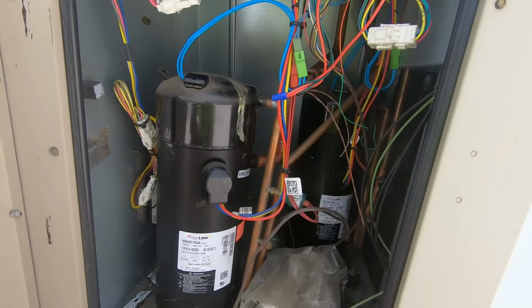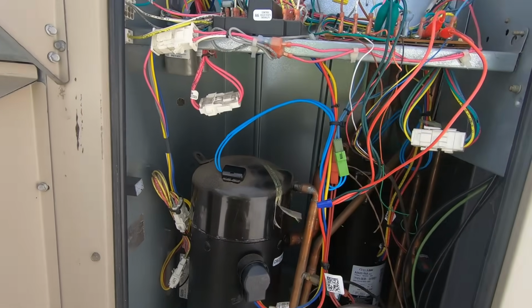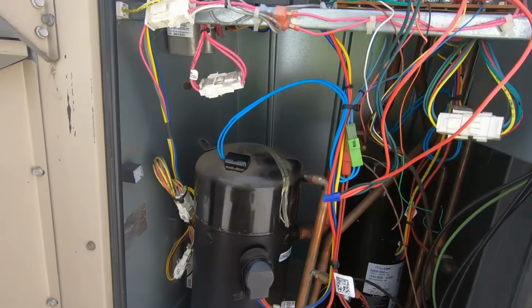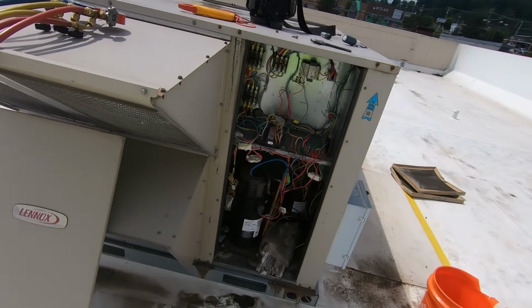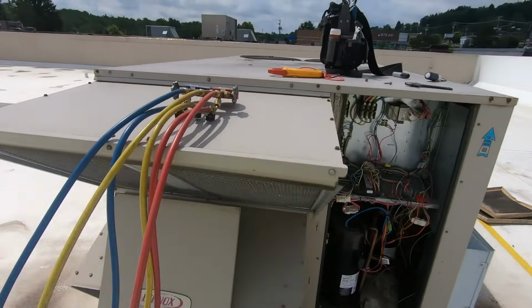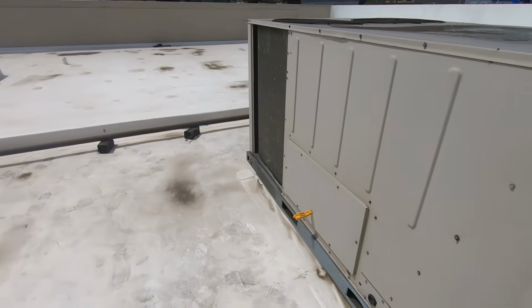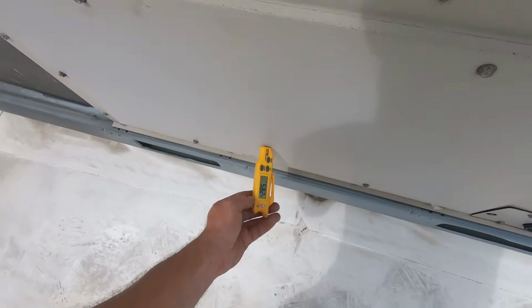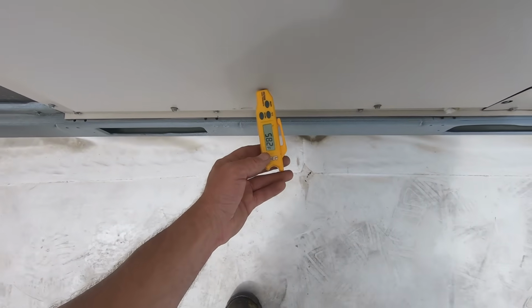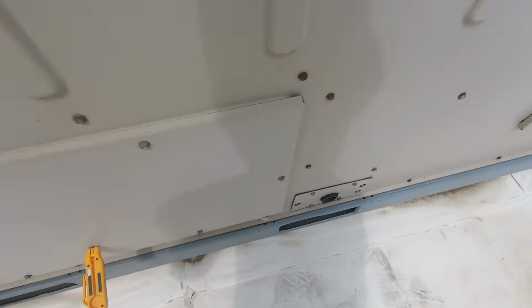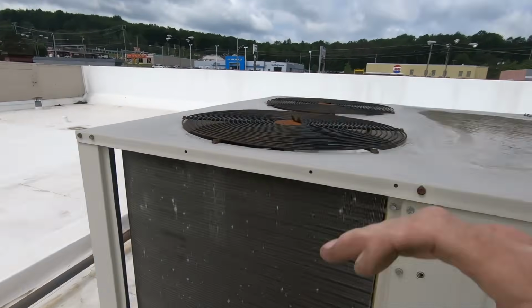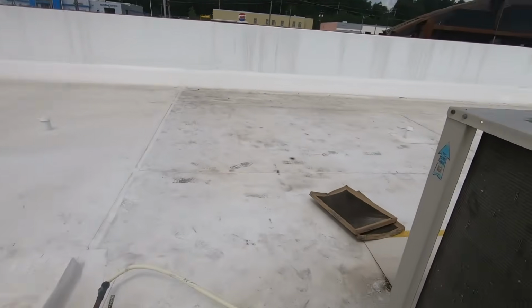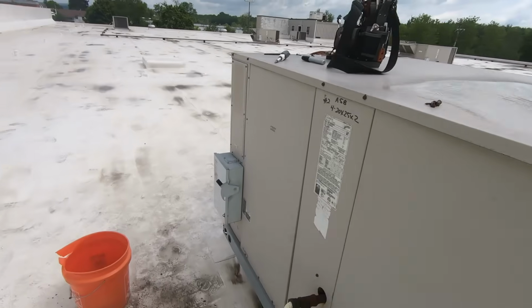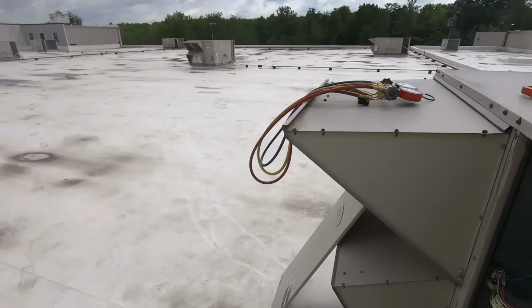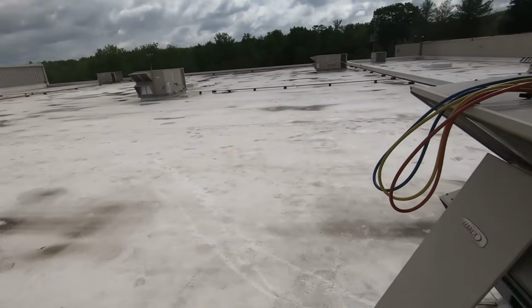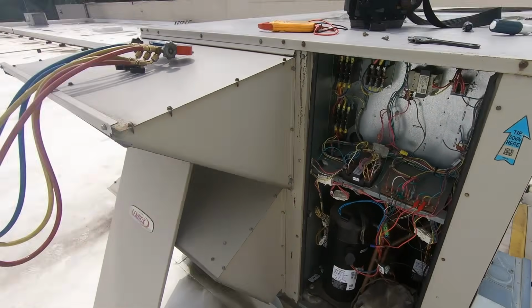Come back, clean it. I always put on the service report after they're cleaned and maintained. There may be more write-ups. So, well, I'm glad that we don't have any major problems with this guy. I think that guy hit the switch and turned the power off to the unit. 58 right now. I mean, it's cooling. I don't know what our return temp is. Not even going to check it until we come back and clean everything. I think I might leave this one run for a bit while I go and start collecting information on 3. See if it trips those high pressure switches.